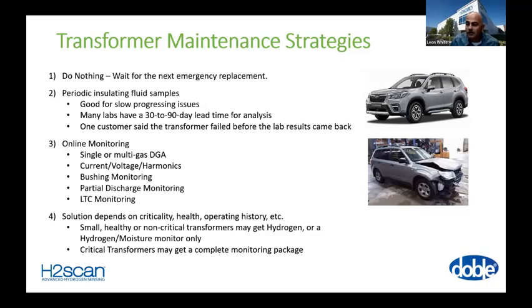So again, online monitoring: people deploy all kinds of different monitoring, single or multi-gas DGA monitors, monitoring your current voltage harmonics, bushing monitoring, partial discharge monitoring, LTC monitoring. There's lots and lots of monitoring available today. And as Moz has pointed out, it's very important that you not only maintain your transformers, you also maintain your monitoring systems. And if the monitoring system is telling you there's a problem, you need to do further analysis to understand what's going on. Do you have any more to add to that, Tony? A few little things, if I may. Sure.